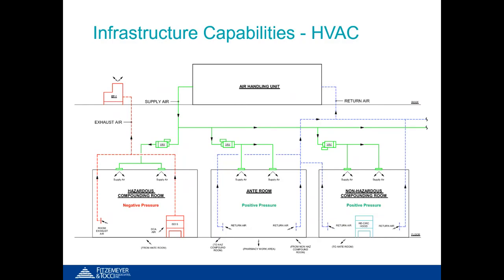This graphic shows a typical layout for a new HVAC system used to comply with the USP guidelines. In this system configuration, the air handler component contains most of the major components. A HEPA filter would be located in the air handler to provide the HEPA filtered supply air. A fan array or multiple fans would be provided to provide the increase in static pressure needed, as well as the reliability and redundancy. Cooling and heating coils would be sized to meet the demands of the space. And in this configuration, supply air is supplied to each individual space through a distributed system using terminal units. The air is distributed from laminar flow devices located at the ceiling.